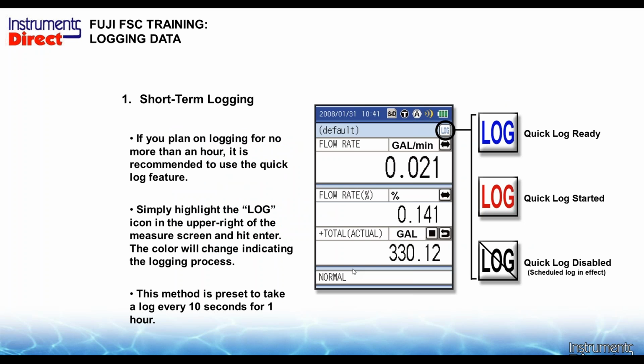And what I mean by that is it's this massive amount of data, and it has a short-term log as well. So if you're up on that ladder and guess what, you forgot your clipboard and your pencil to write something down, you can actually do a short-term log just by pressing the quick log button. If you press that button, it'll begin to log data, take screenshots basically of the data that you have. It's preset to take a log every 10 seconds for up to 1 hour. So that's just a quick log if you don't have the ability to go in there.